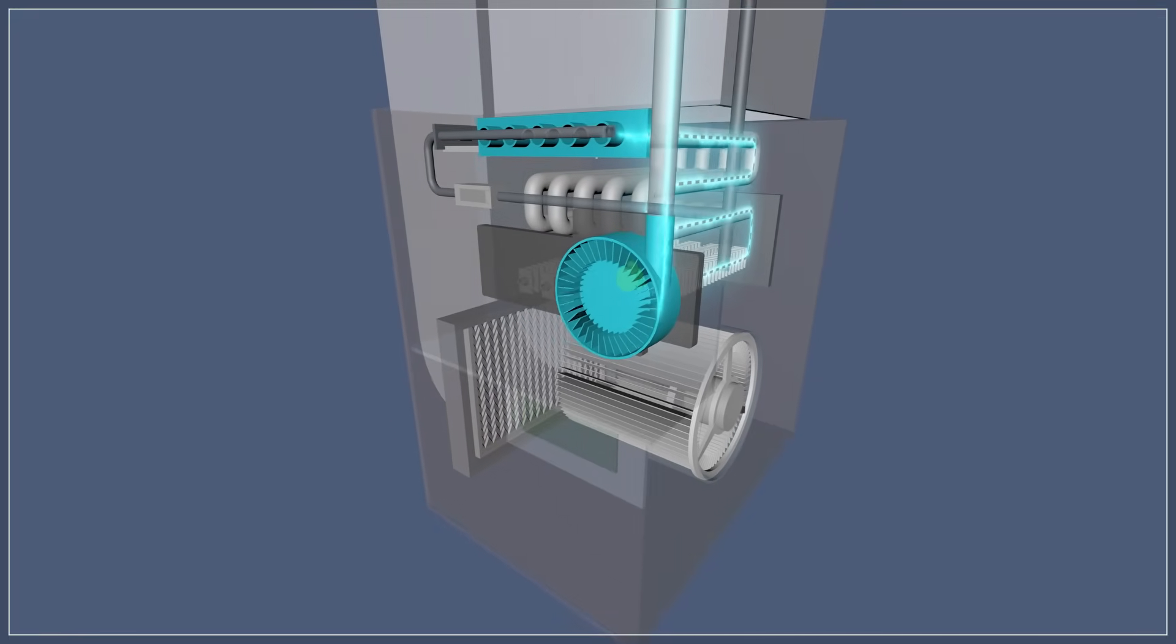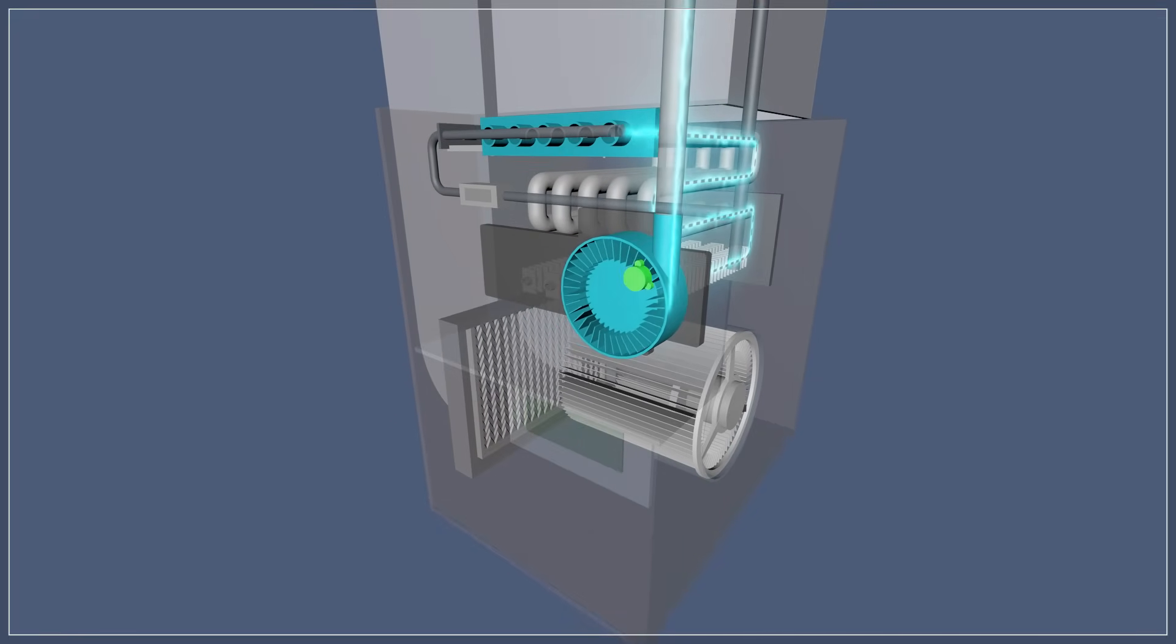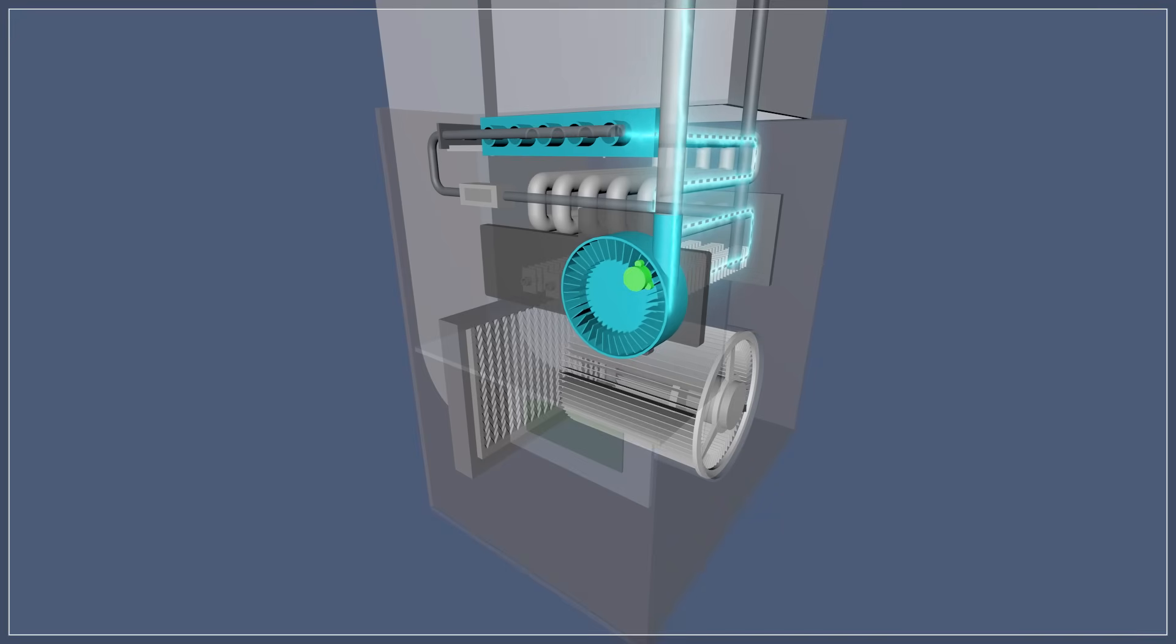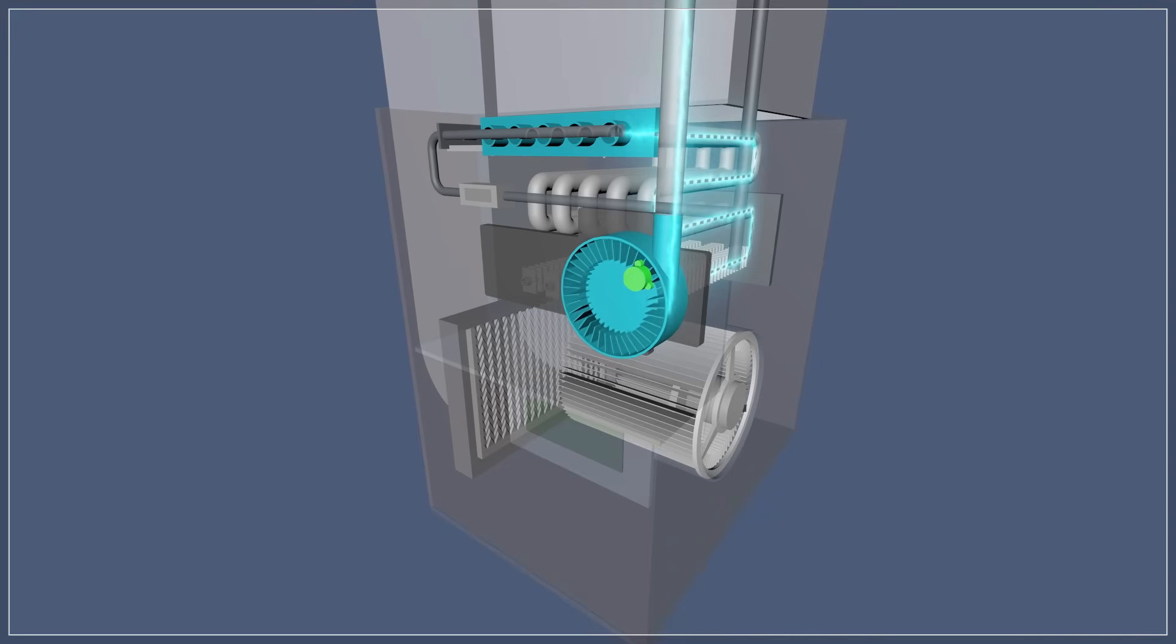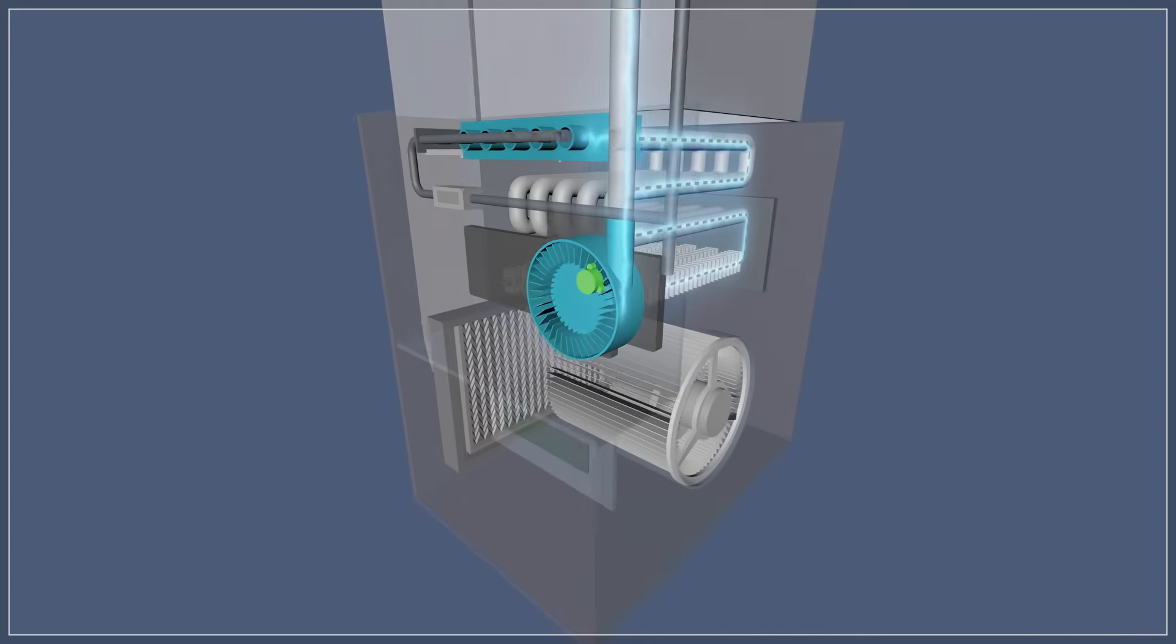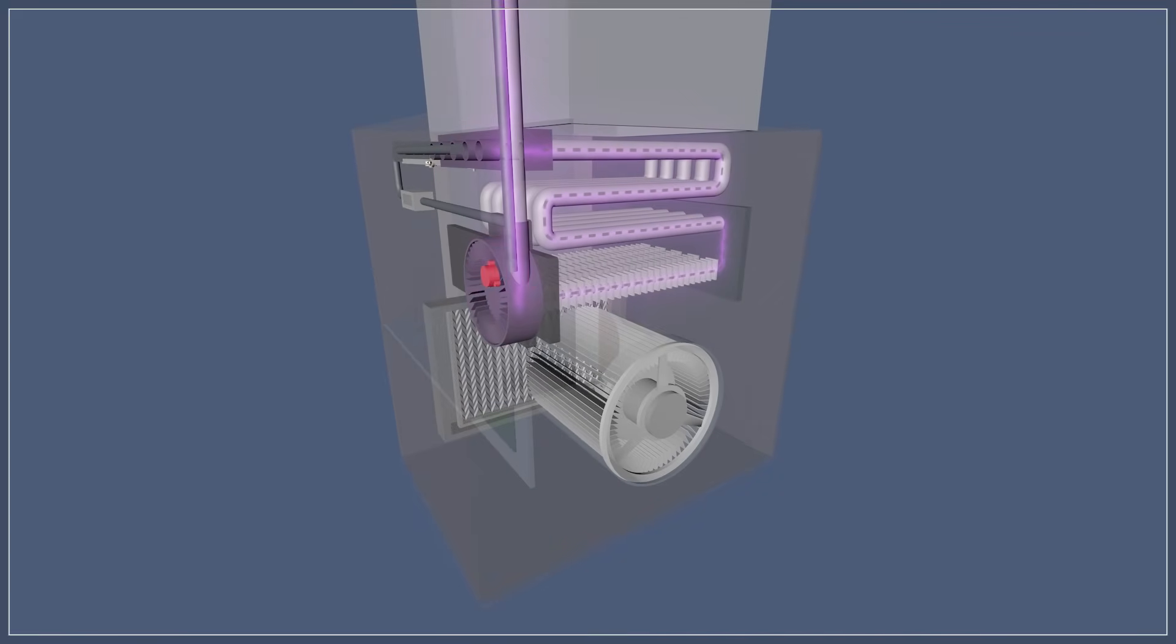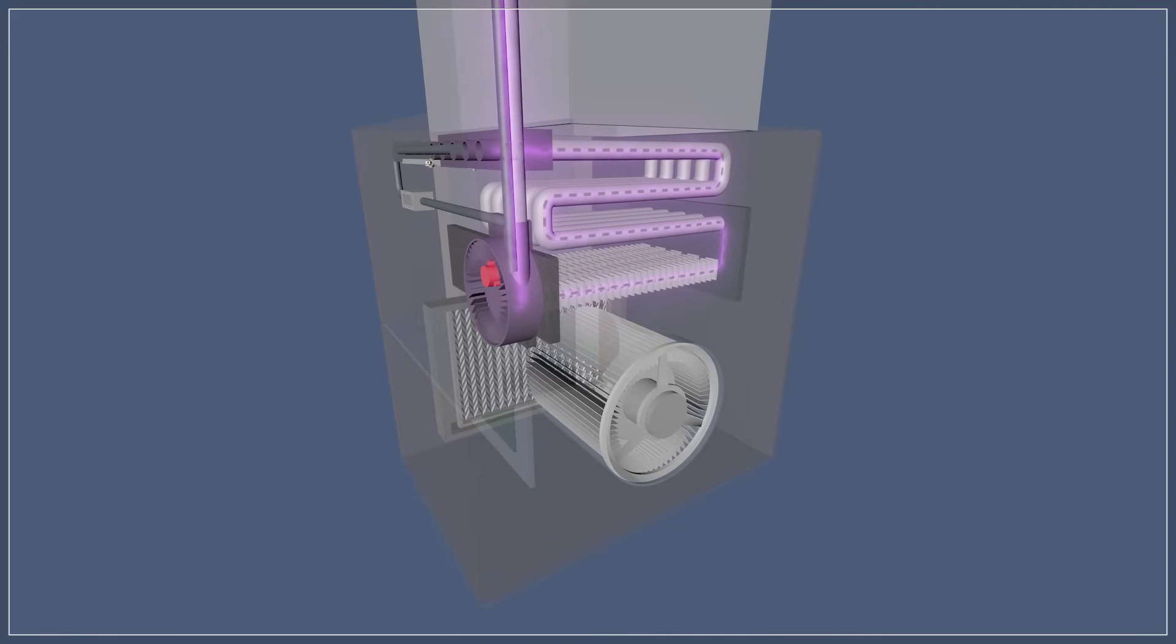When the draft motor reaches full speed, the pressure switch will close, allowing for the sequence to continue. The pressure switch ensures that there is enough air flow inside the heat exchanger to safely operate the furnace. If the pressure is low, the switch will stay open and will prevent the furnace from igniting.